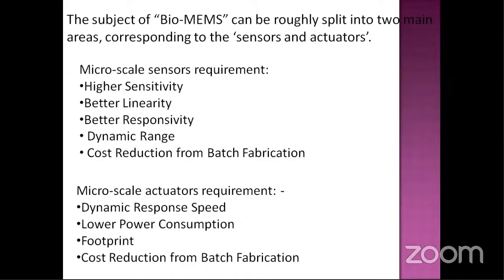So, what are the requirements for a MEMS sensor and actuator? The sensor should have higher sensitivity to the target parameter, better linearity, that is, hysteresis should not be that much. Then better responsivity, that is, an immediate response should be there. The output should be displayed, like the amount of sugar, glucose availability, within a fraction of a second. Dynamic range. The dynamic range is very important because very small changes should also be measured by the MEMS sensor. Very small ranges, 0.001 ranges. Changes should also be identified. That is very important when you are using a bio-MEMS sensor.